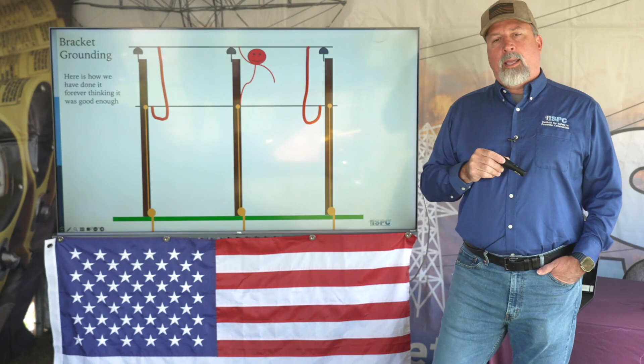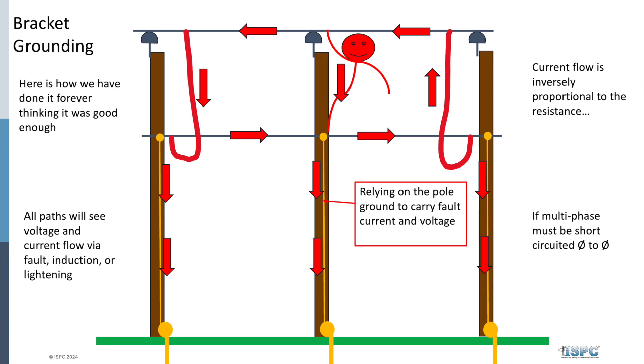Current is inversely proportional to the resistance, so it's very important you understand this. If you're doing this bracket grounding—and I know for a fact, including at the utility I worked for, up until equipotential grounding became required, back around 2014 when the OSHA regs changed requiring equipotential grounding—at the company I worked for, if you had this bracket-grounded setup, de-energized, you could work in leather gloves. You didn't need your rubber PPE.